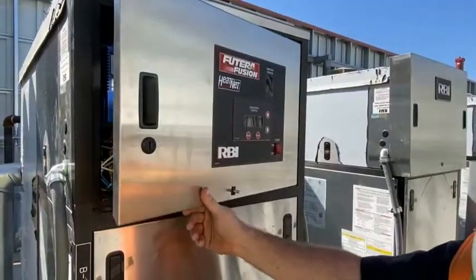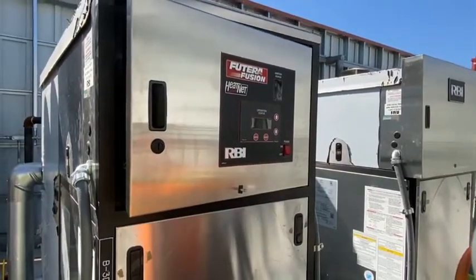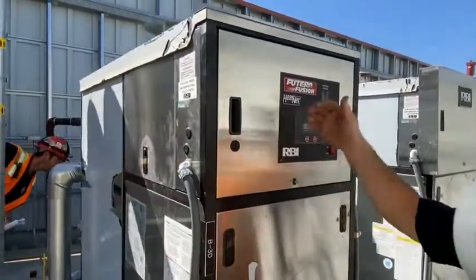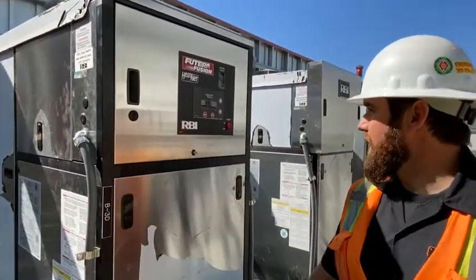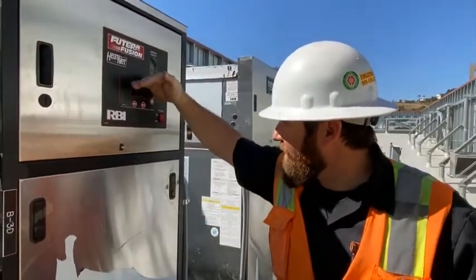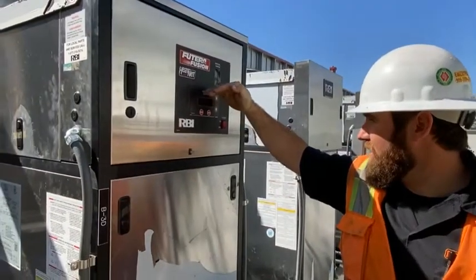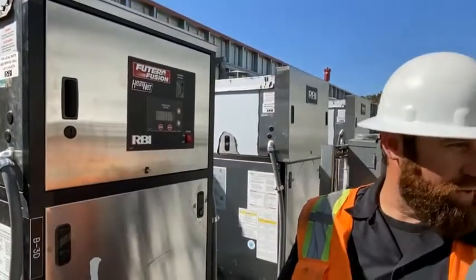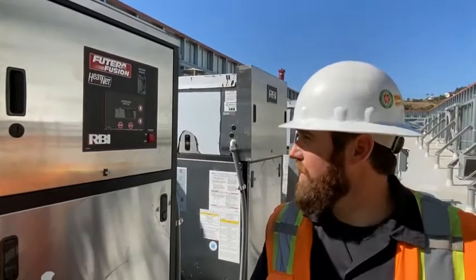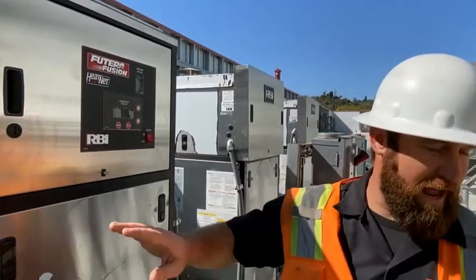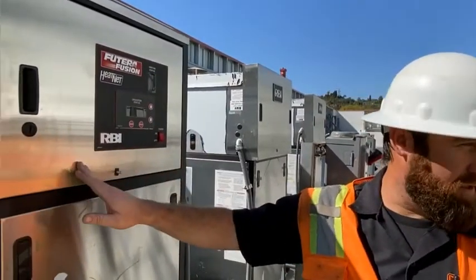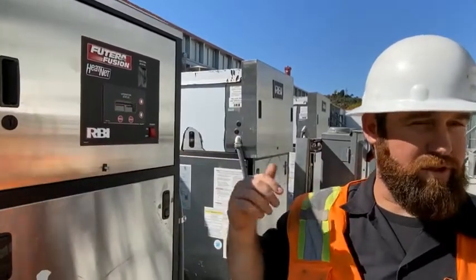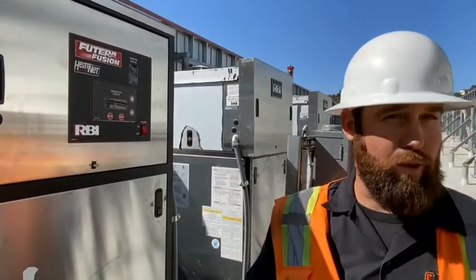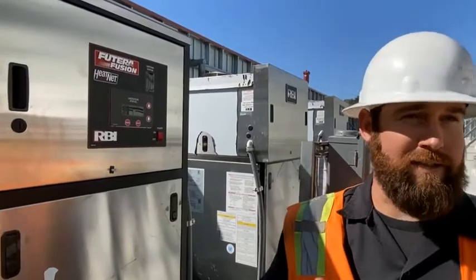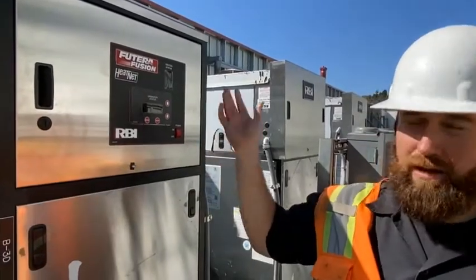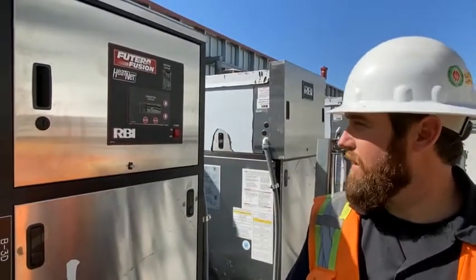Alright, so these are going to be, I believe, BMS controlled. This is the master boiler. These are the two slaves. Right now we have a 150 degree set point on there. I believe you'll be able to control that set point through the BMS. If anything should happen to the BMS communication to these boilers, the boilers will switch over from remote mode to local mode, and they'll run at their own set point, which they all have individually set.